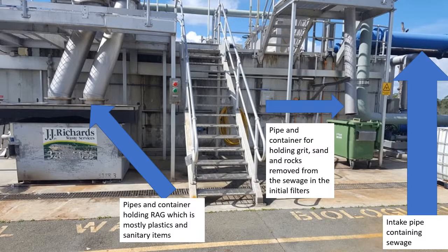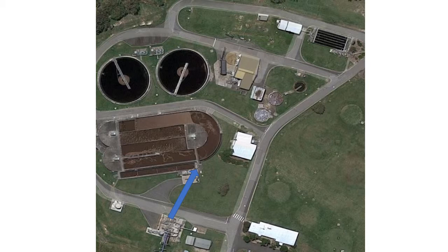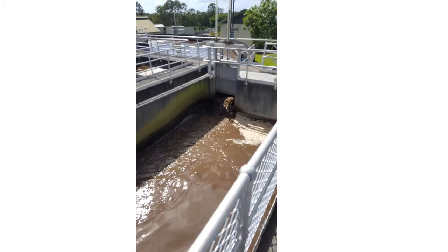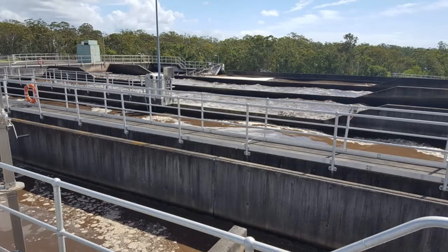The next stage is secondary treatment, removal of nutrients, and introduction of coagulants and flocculants. The sewage makes its way into the aeration tanks, as shown here, which removes contaminants such as nitrogen and phosphorus through anaerobic and anoxic processes. These processes are caused by special bacteria that oxidize ammonium and ammonia into nitrite, which is then also oxidized into nitrate, NO3. This process occurs under aerobic conditions, which means with the presence of free oxygen.